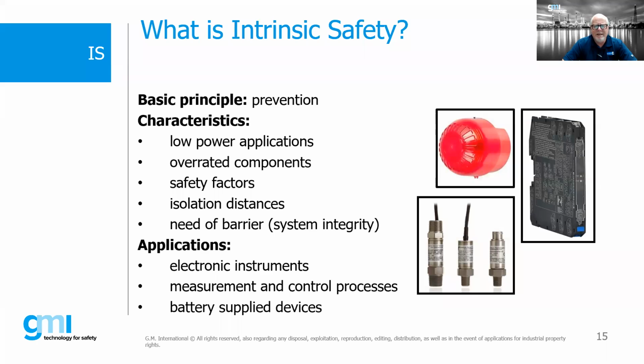The applications are basically electronic instruments, measurement control processes, battery supply devices. Anything that we can be measuring in many cases or controlling with low voltage instrumentation type products can basically be made intrinsically safe. The important thing to note is intrinsic safety, while it is widely used, cannot be used for every application. When we get into high power applications, intrinsic safety is not a protection technique. We have to look at different protection techniques. But basically, if we're talking about 1 watt of power or less, that is more or less our cutoff point where we can start looking at the use of intrinsic safety.